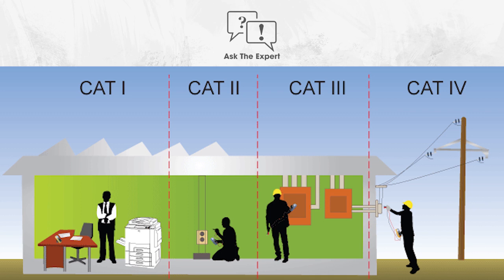The final one I'll speak about is Category 4. It's the highest level, again for three-phase, mainly operating around the utility sector. This is where you might have outdoor connections and want much more safety elements taking place. Typical ones would be around consumer units, electricity units, maybe even service entrances - all these things where utilities need to be much more tightly controlled, potentially at much higher voltages. That's why these category ratings are important, aligning with making sure your electrical meter is actually relevant to be used in those specific categories. That's the most critical thing, because we're talking about potentially hazardous and dangerous areas where high voltages could be present, and there's always an element of risk. So these need to be taken into strong consideration.